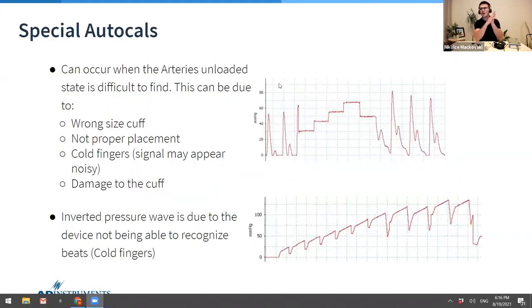So with this system itself, as we're all depending on the fingers to be nice, the arteries to be nice and plump and easy for light detection to see, quite a few things could go wrong that we need to be aware of. One thing is if it's the wrong cuff size. If the size is clearly too large for a subject's fingers, then the values will be greatly diminished and undervalued. So that's why it's important to look into the cuff size guide, but also if you do notice that the signal looks quite noisy, then I would recommend to drop the cuff size, and you want to see a signal that's fairly clean like this. It's nice and uniform. Improper placement is also a big factor. As I mentioned before, we want to make sure that the light's going below the bone. So that just takes practice to get that in the right position there. A manual will be supplied with you when you are looking into this, of course.